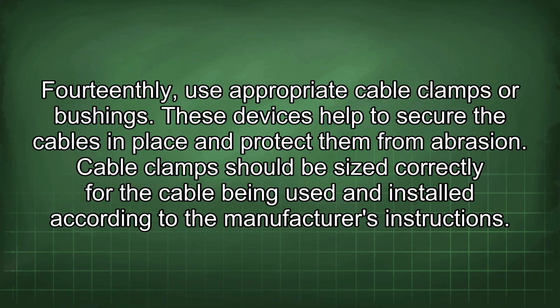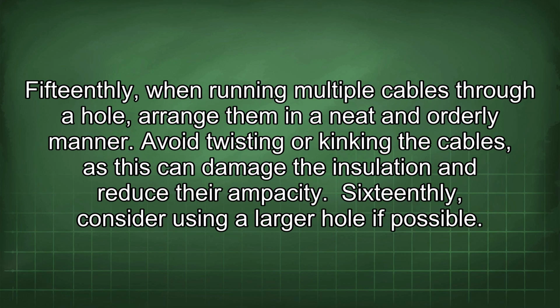14thly, use appropriate cable clamps or bushings. These devices help to secure the cables in place and protect them from abrasion. Cable clamps should be sized correctly for the cable being used and installed according to the manufacturer's instructions. 15thly, when running multiple cables through a hole, arrange them in a neat and orderly manner. Avoid twisting or kinking the cables, as this can damage the insulation and reduce their ampacity.